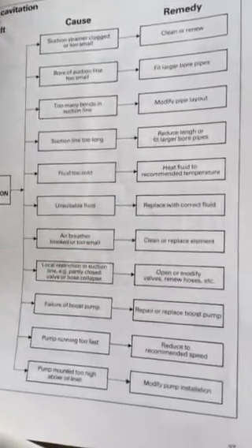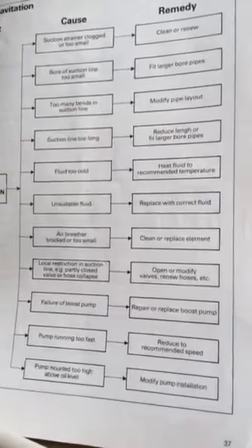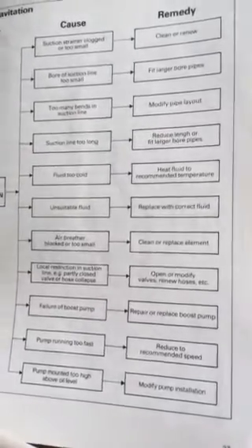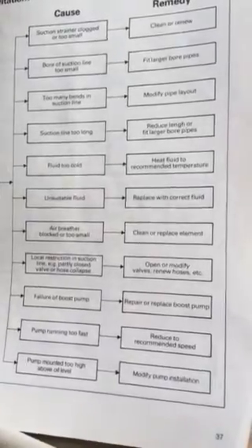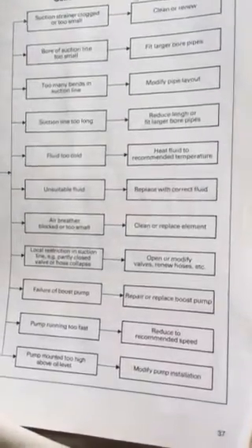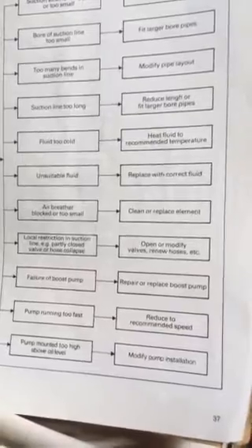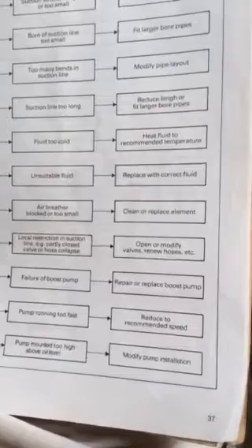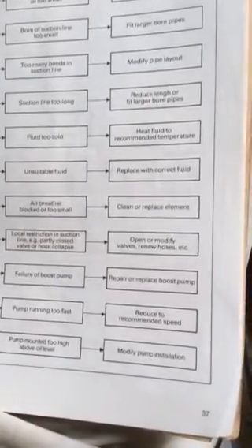Fluid too cold, heat fluid to recommended temperature. Unsuitable fluid, replace with correct fluid. Air breather blocked or too small, clean or replace element. Local restriction in suction line, for example partly closed valve or hose collapse. Open or modify valves, renew hoses, etc.